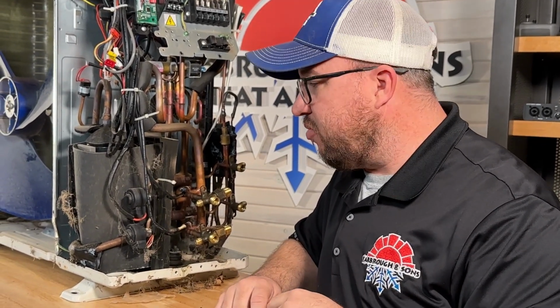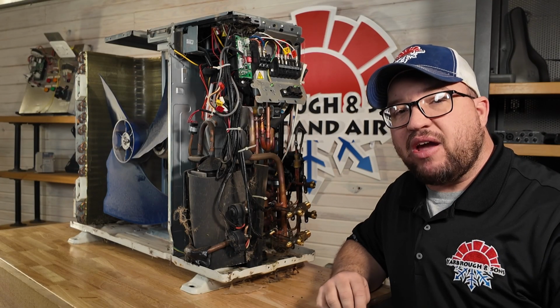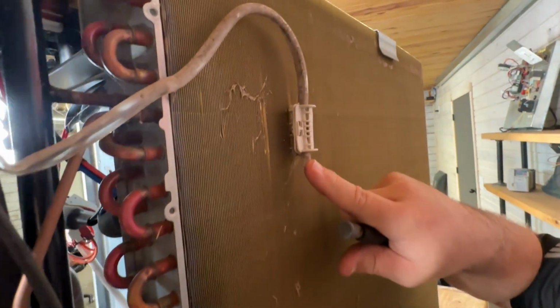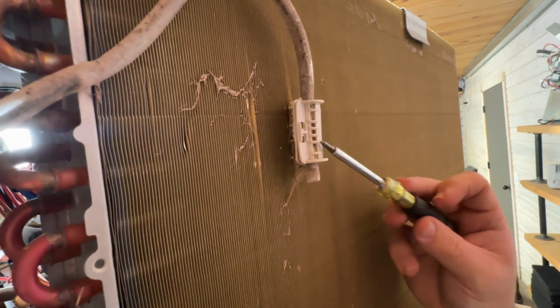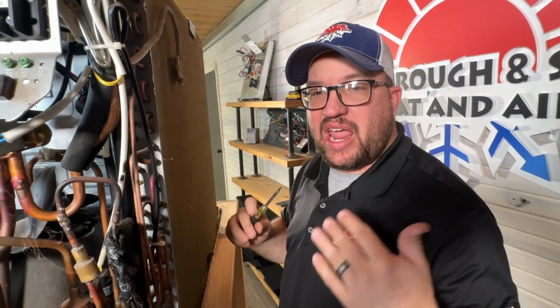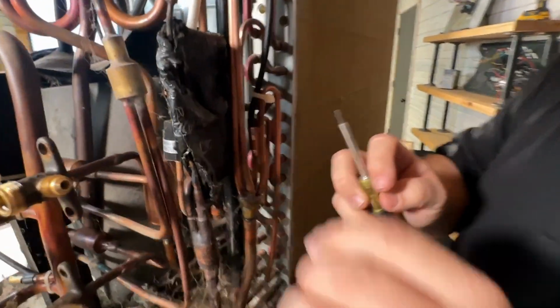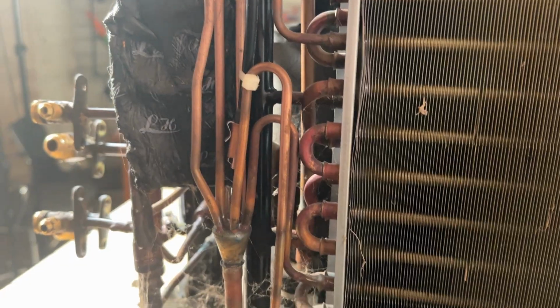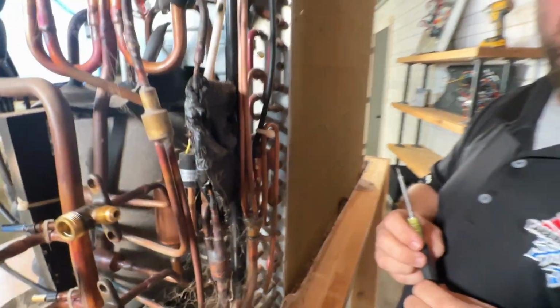So other things we're going to look at right now, we're going to look at a couple sensors we have here to help calculate what we're actually needing this system to operate at. So whether we want to ramp it up or ramp it down, these sensors are what's going to help calculate that. Right here, we're going to actually have a thermistor, and this thermistor right here is for checking the actual outdoor air. So we want to know what the ambient air is outside right before we're going into that coil. That way we can calculate it, and it's going to take that information to the control board and say, hey, I got this cold outside, I probably would suggest running about this speed. And then this right here is an actual coil sensor, and it's just reading that coil temperature, and that's also going to factor into saying, yeah, we should probably run it at that speed.